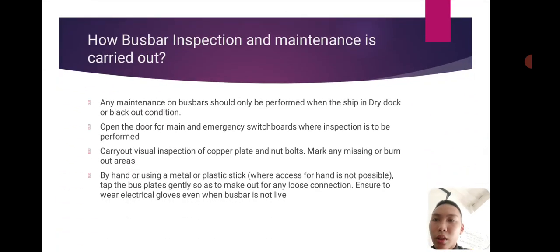How bus bar inspection and maintenance is carried out. Any maintenance on bus bars should only be performed when the ship is in dry dock or blackout condition. Open the door for the main and emergency switchboards where inspection is to be performed. Carry out visual inspection of copper plates and nut bolts. Mark any missing or burned out areas by hand or using a metal or plastic stick where access by hand is not possible. Tap the bus plates gently and make out any loose connection. Ensure to wear electrical gloves even when the bus bar is not live.